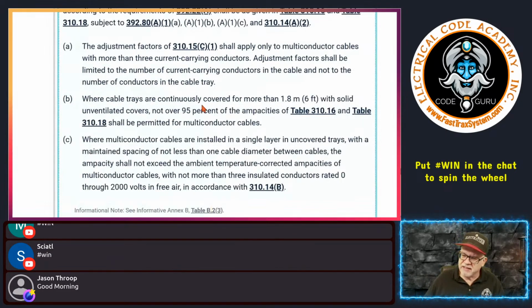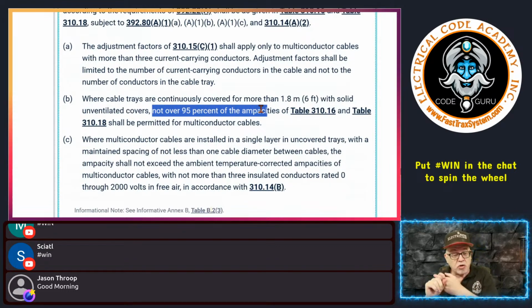It says that if that's the case, then it's not over 95% of the ampacities in 310.16. Okay, so whatever the ampacity is for those cables in that cable tray, if that's the case, then whatever the ampacity is, you can't exceed 95% of that ampacity. Okay, so that conductor now doesn't have the same ampacity; it's reduced.